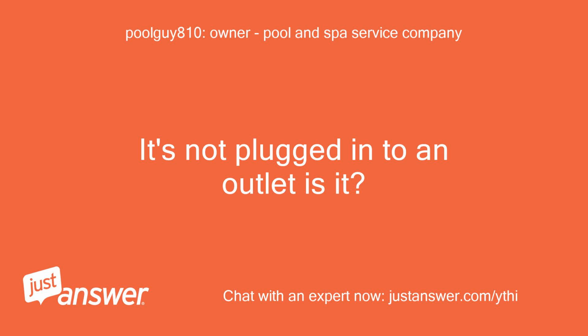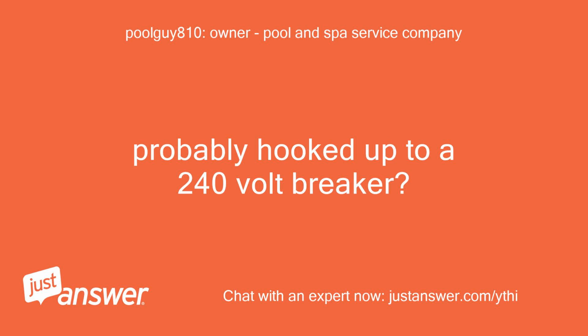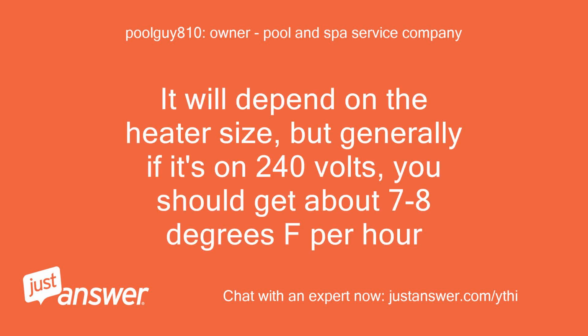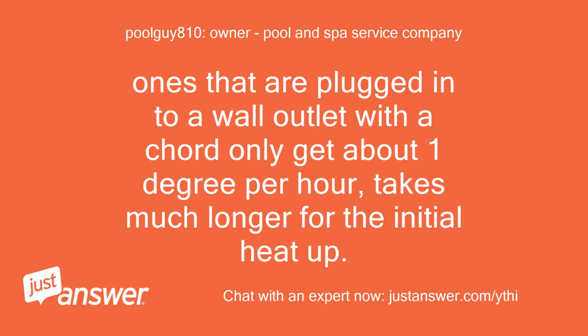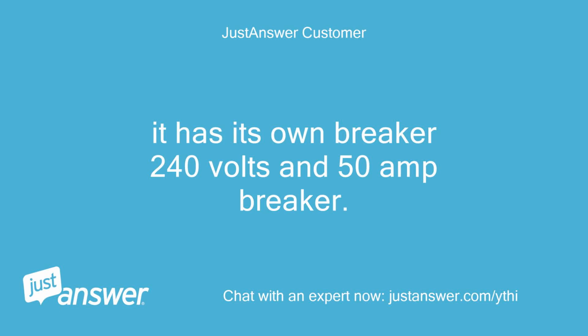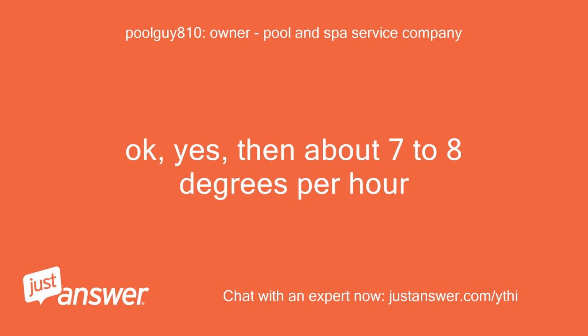It's not plugged into an outlet, is it? Probably hooked up to a 240-volt breaker? It will depend on the heater size, but generally if it's on 240 volts, you should get about 7 to 8 degrees Fahrenheit per hour. Ones that are plugged into a wall outlet with a cord only get about 1 degree per hour, takes much longer for the initial heat up. It has its own breaker, 240 volts and 50 amp breaker. Okay, yes, then about 7 to 8 degrees per hour.